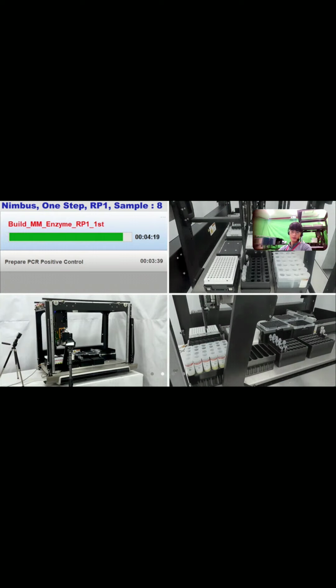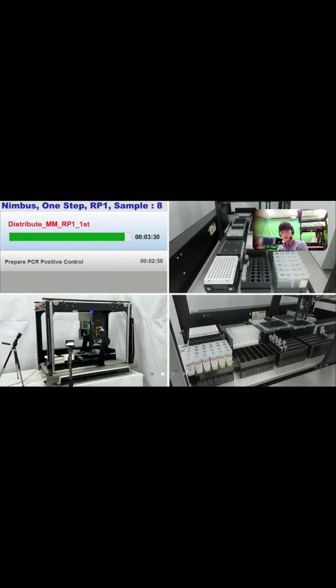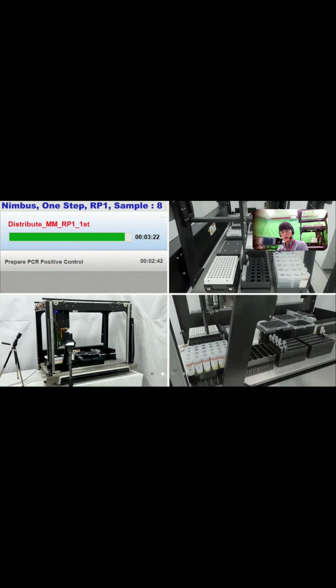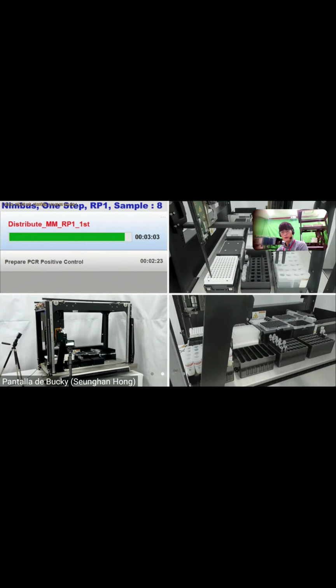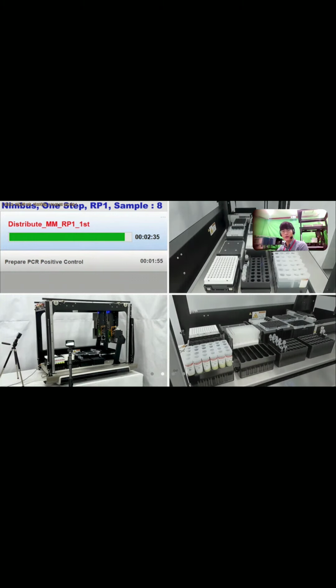Okay, the difference between the negative control and the others is that when the negative control is aspirated, the machine uses the CLLD function, and the others just use a fixed height, okay? So the teaching for the PCR3 is very important. And the 4 kinds of liquid are mixed in right now. It's time to distribute the master mix, 18 microliter. 1, 2, 3, 4, 5, 6, 7, 8, 9, 10. 9, 10 for the control positions.